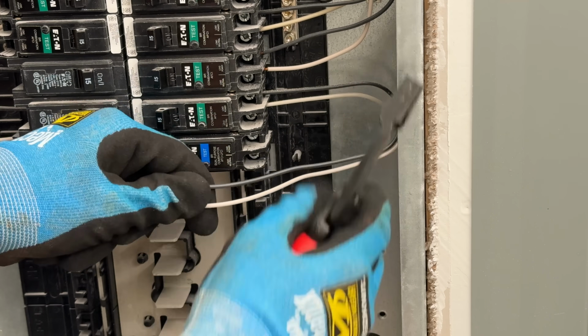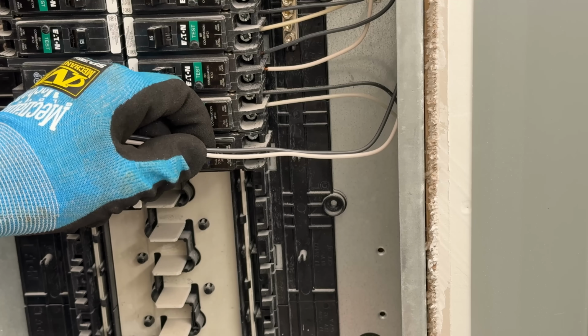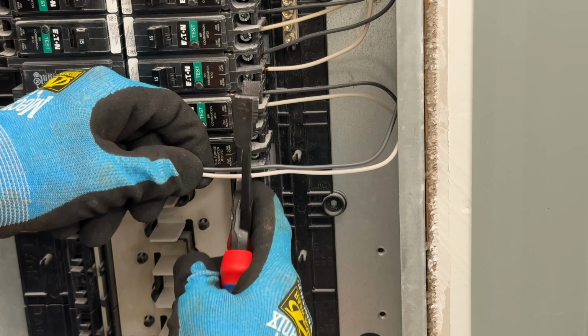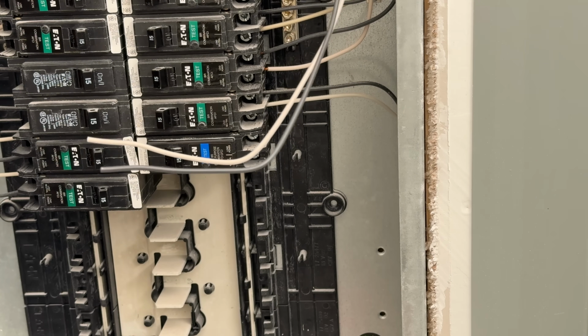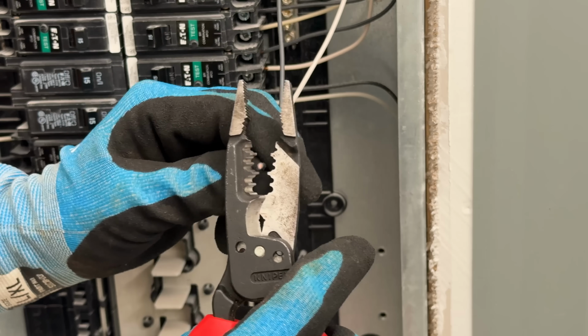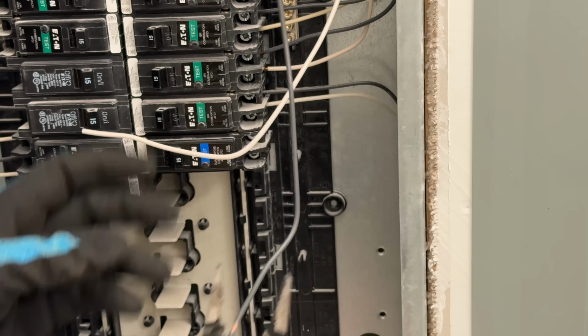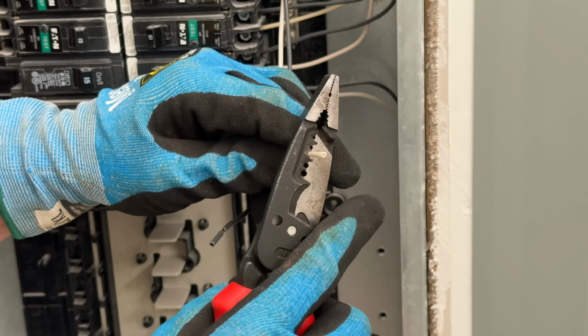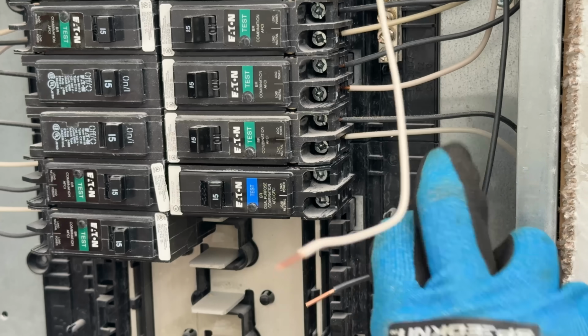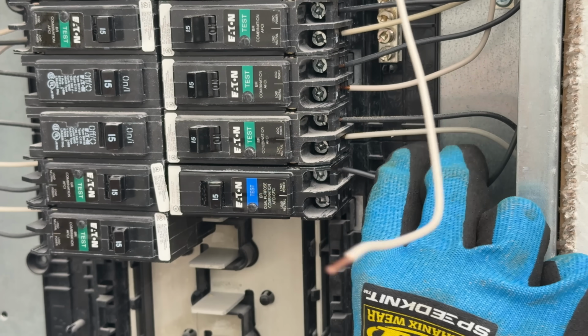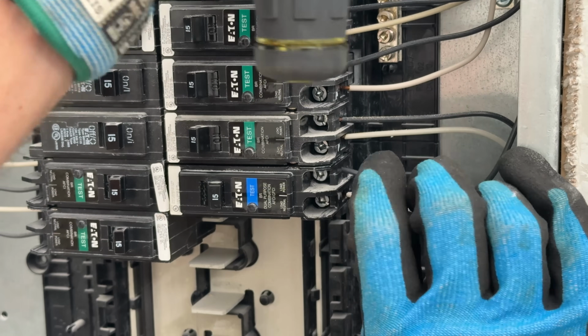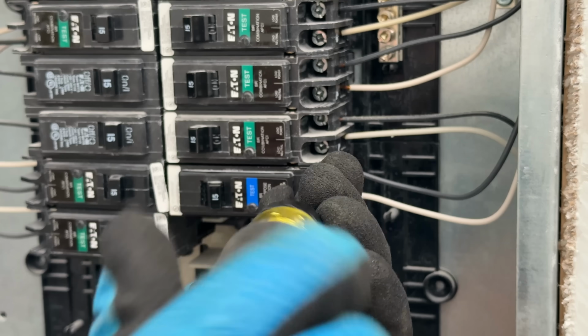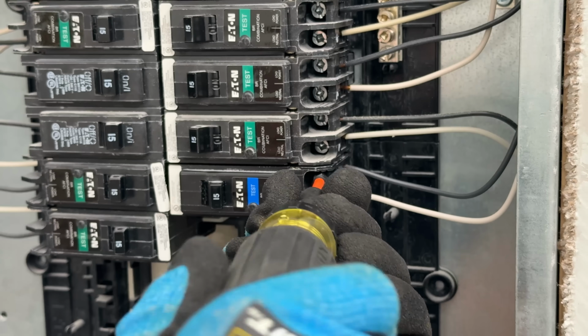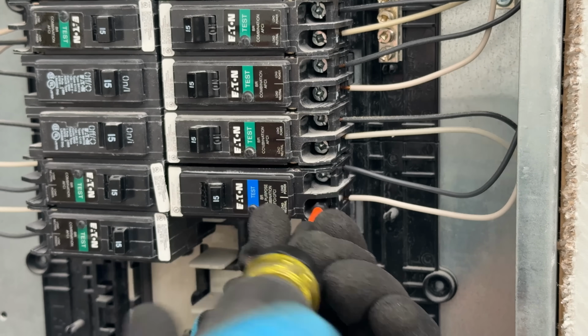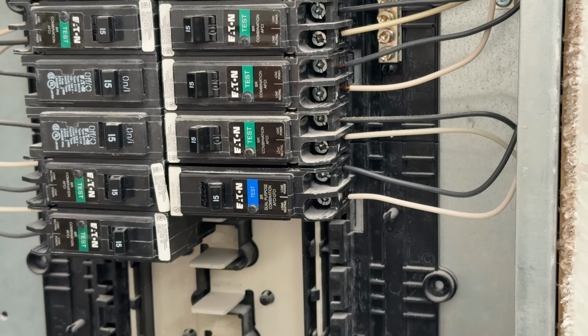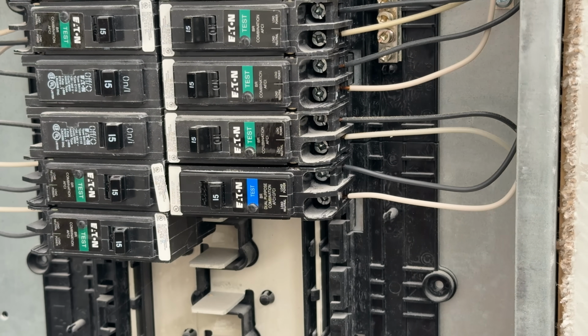Once you have that, you can just go ahead and take your wire cutters here. These are Knipex hybrids, and just cut that to length, stripping those off so we can land both the hot and the neutral. Remember, we need both of those since this is a dual purpose AFCI and GFCI breaker. You'll land those within here, and then we'll use that 15-in-1 again with a number 2 square drive, making quick work of tightening down each of our 2 screw terminals to finish off this breaker relocation.